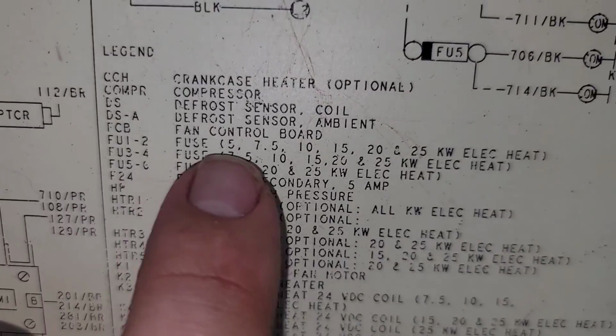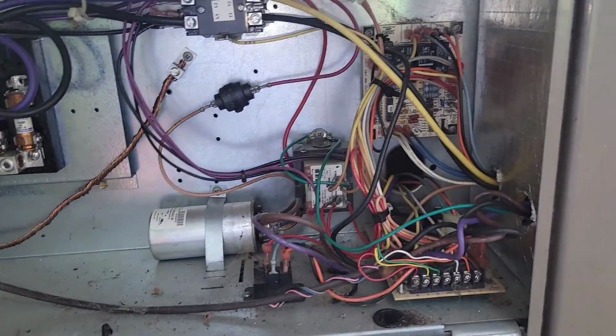See, FCB says right here, fan control board. Recheck the heater kit. No heaters are coming on, energizing. It could be that control board, but right now it looks like it's the thermostat. So it's on the cooling operation, but we've still got that power going between C and W. So if it ends up sending 24 volts to that W terminal, then we're going to be energizing some heat strips. So what I'm going to do is a process of elimination.